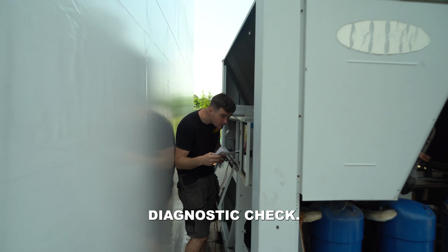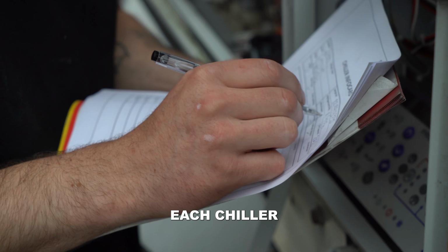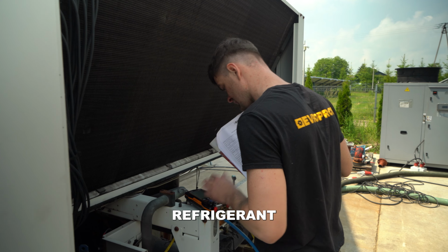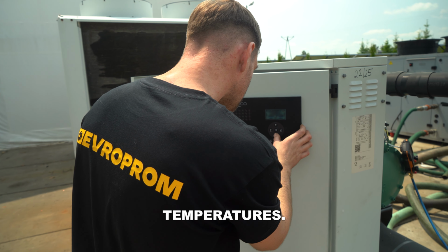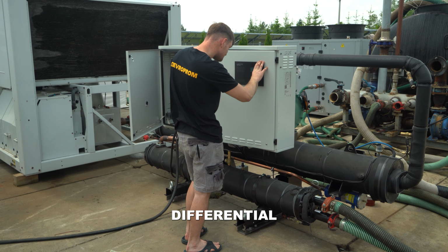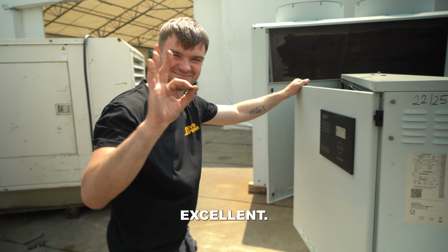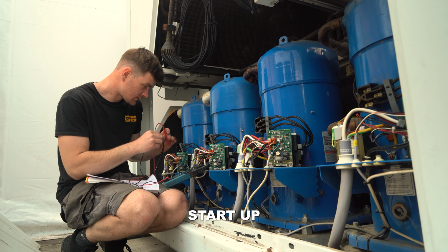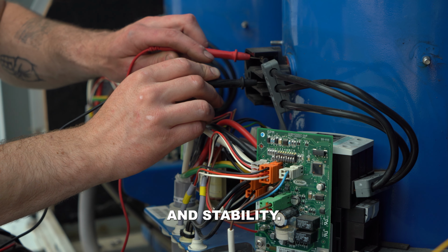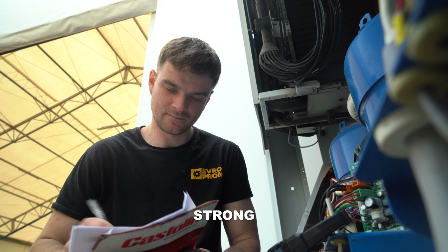Then comes a full diagnostic check. We test each chiller against 7 key parameters: refrigerant pressure, heat exchanger temperatures. Is the temperature differential perfectly within range? Excellent. Compressors, startup, current levels, and stability. We check that the heart is beating strong.